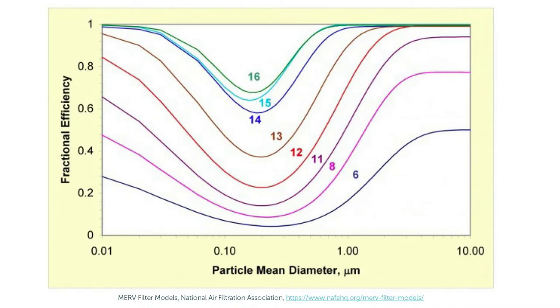As mentioned earlier, the higher the MERV, the better the filter is at removing particles from the air, especially those particles in the 0.1 to 1 micron problematic range. This chart shows the initial modeled fractional efficiency of MERV-rated filters in removing particles. That basically means how good they are at removing the particles.